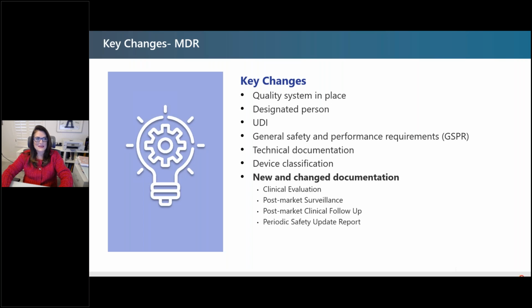But the MDR, some of the key things with MDR specifically is that I found the requirements for all device manufacturers have to have a quality system in place, as well as having a designated responsible person for regulatory compliance. Additionally, every device now has to have the unique device identification or UDI. And the essential requirements were replaced by the general safety and performance requirements. And there were changes, which are a lot of what we do every day, to the technical documentation and new documentation requirements specifically for clinical evaluation, post-market surveillance, post-market clinical follow-up, and the periodic safety report.